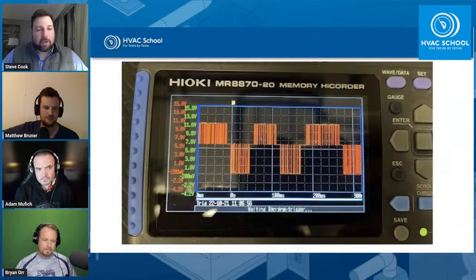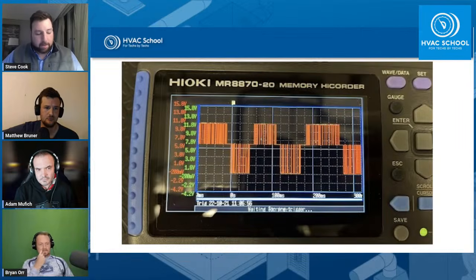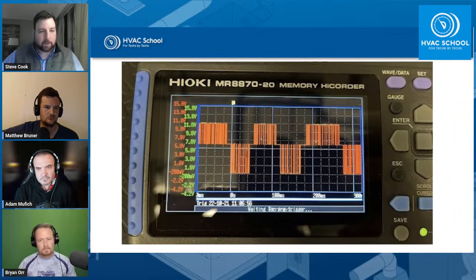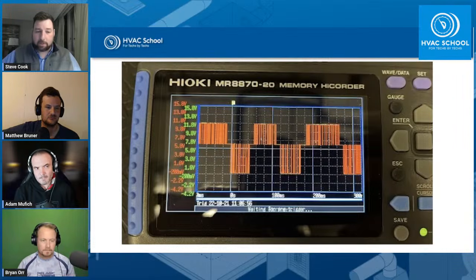The oscilloscope thing is interesting - it's neat to see, but you don't really need to dive that deep. Typically, if you have a communication fault - let's say the most basic case, they ran solid core wire and you're not communicating. So you're telling it to run the fan and it's not running, and you may not be getting a fault code.